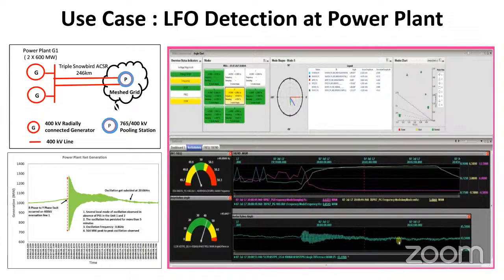We get a lot of information from the PMU about when the damping is going down. You can see the oscillation in those plots. The red curve, which was going up, suddenly comes down, representing the damping going to nearly zero. Initially the damping was quite very low, and that's what the PMU captured.